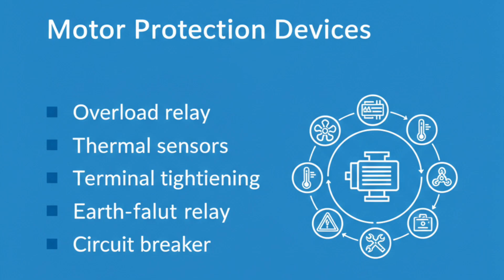Protection devices are extremely important in preventing catastrophic failures. Overload relays protect motors against prolonged overcurrent, while thermal sensors embedded in windings trip the supply if temperature exceeds safe limits. Earth fault relays detect leakage current and prevent electric shock hazards. Phase failure relays protect against single phasing. Circuit breakers and fuses isolate the system during short circuits. Regular testing and correct setting of these devices are essential.